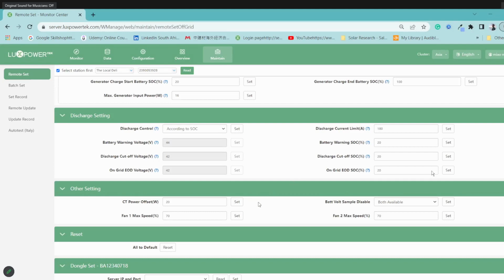Okay. For the fans, if you have a situation with your LXP, sorry, SNA 5000, and the fan sounds like a jet and it's extremely loud, then in most cases, we either need to replace the fan, change the control board, or change the interface board. So that is an abnormal activity. So even if it's spinning extremely fast, and I mean it's very, very loud, then even if you adjust it, yeah, it will have no effect, okay? But in most cases, like if your inverters are working, let's say you've got power coming from the panels, batteries being charged, load is coming through, then all three fans go on. So each fan represents a different function that's happening. That sound that you get, it's normal. It will sound loud, but it's not as loud as what I'm explaining over here. It's extremely loud when this happens.